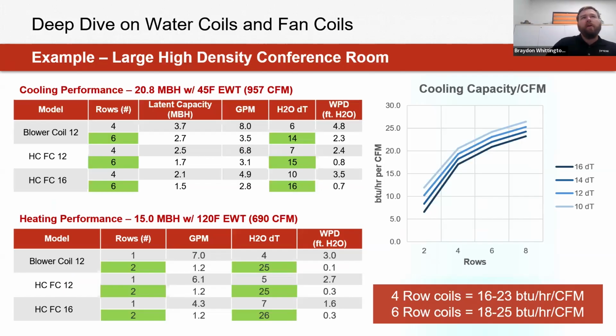So if we were to look at plotting out both our cooling performance and heating performance for these blower coils and fan coils at different rows or sizes, at those same airflows for both our cooling as well as our heating side, we can start to evaluate, hey, first, are we achieving our capacity targets for this system? Is this within a delta temperature that's ideal for a heat pump system, let's say for your heating performance, or for our chiller for our cooling performance?